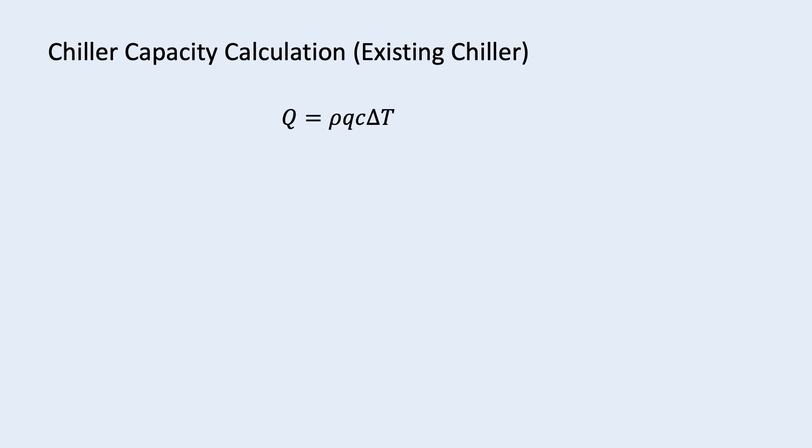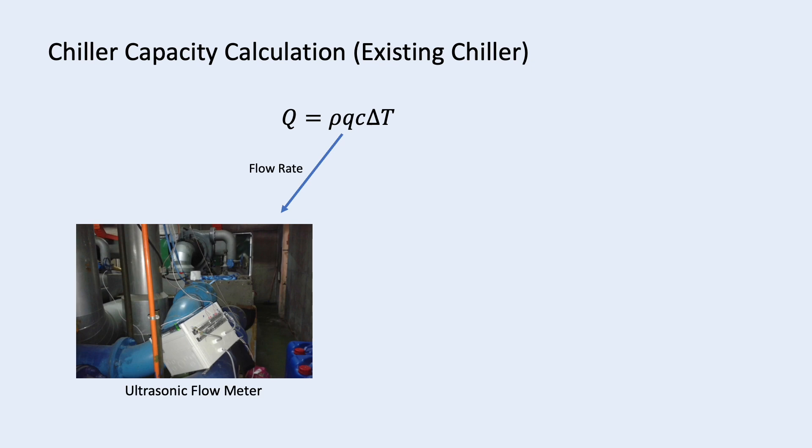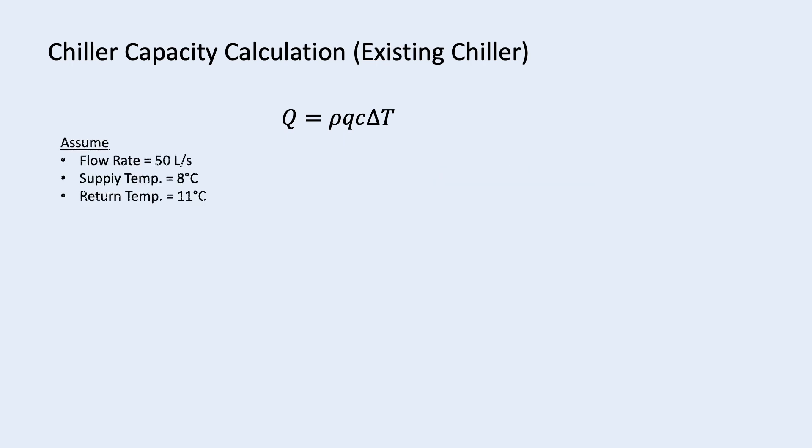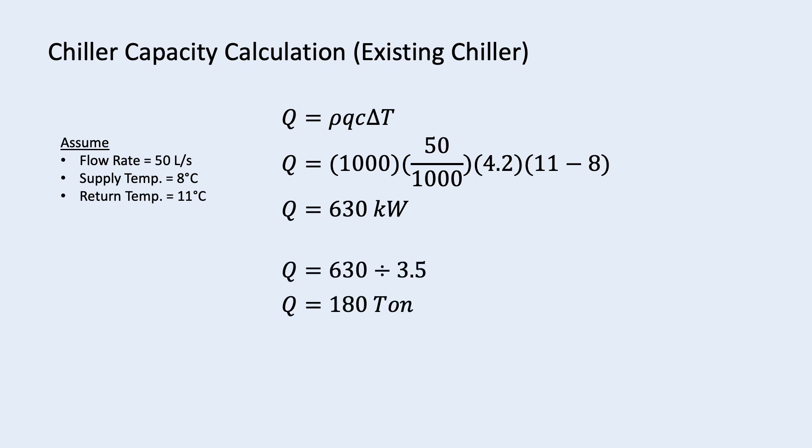For existing chiller, if you want to calculate its current capacity, the same formula can be used but you need to measure the flow rate across the chiller and the chilled water supply and return temperature. Assume you measure the flow rate is 50 liters per second and the supply and return temperature is 8 and 11 degrees Celsius. Using the equation, the chiller capacity is 630 kilowatt. Divide it by 3.5 and you get 180 ton.